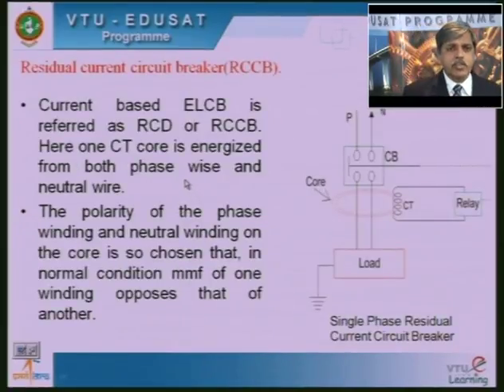Then I have a residual current circuit breaker, called RCCB, current based leakage circuit breaker, okay, earth leakage circuit breaker, referred to as RCD or RCCB. Here one CT core, current transformer core, okay, is energized. I have a CT here, it is energized from both phase wire and neutral wire. The polarity of the phase winding and neutral winding on the core is so chosen that in normal condition the MMF of one winding opposes that of the other.